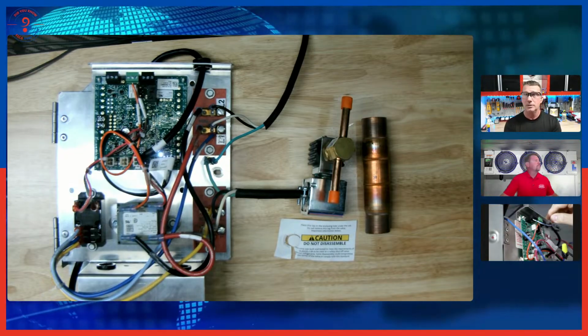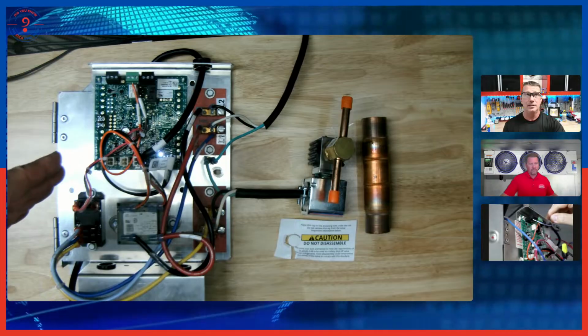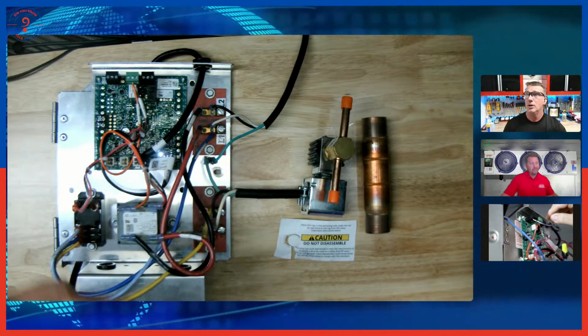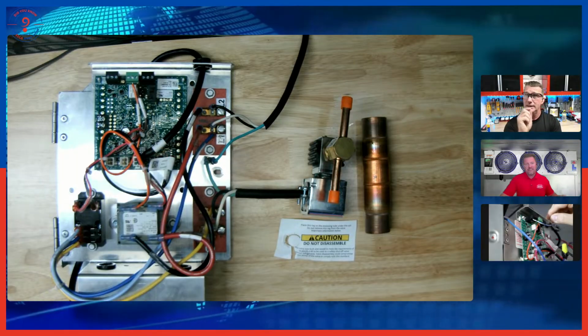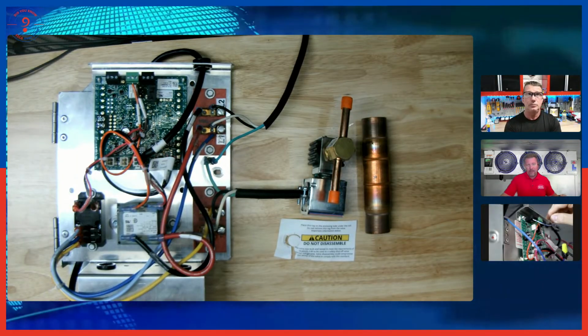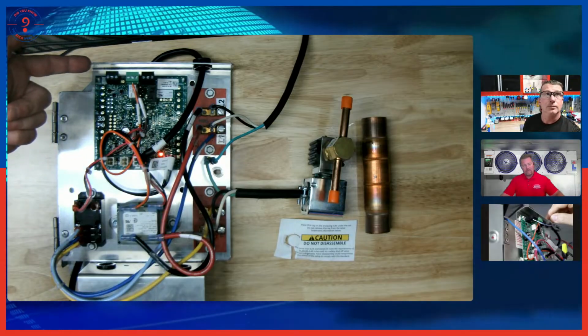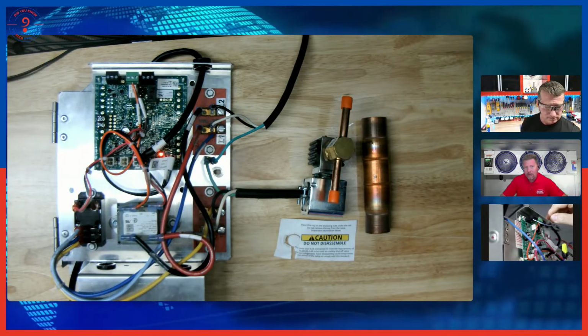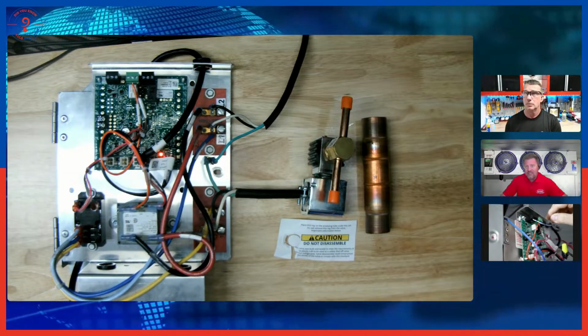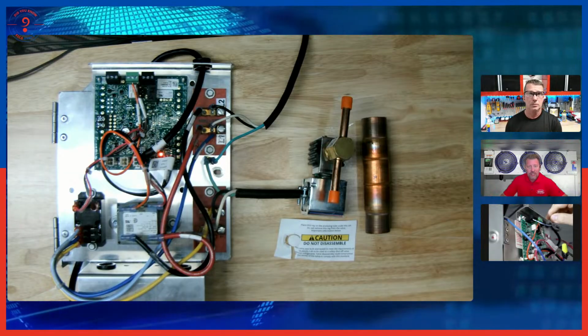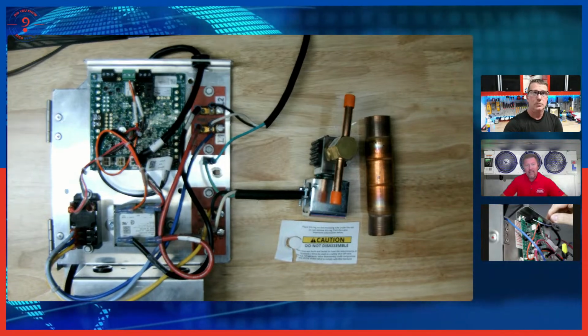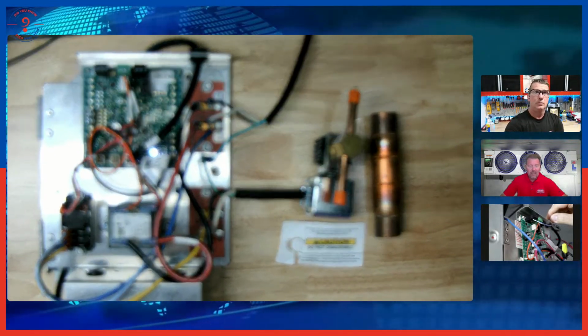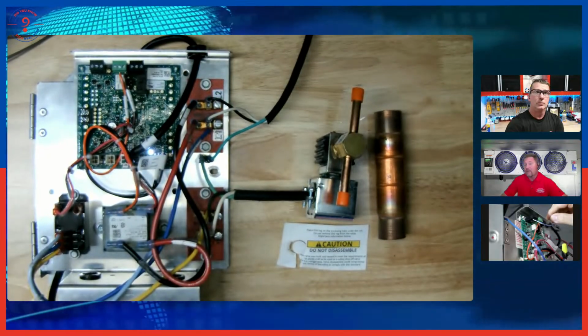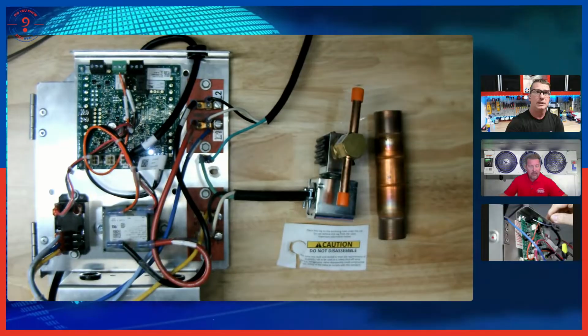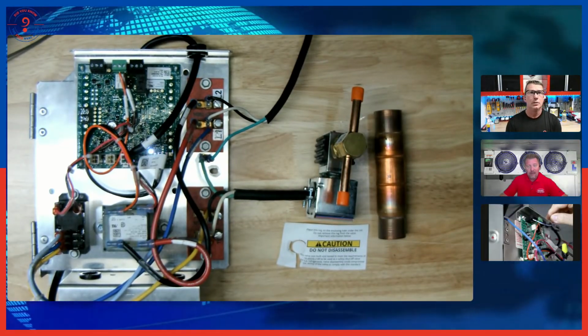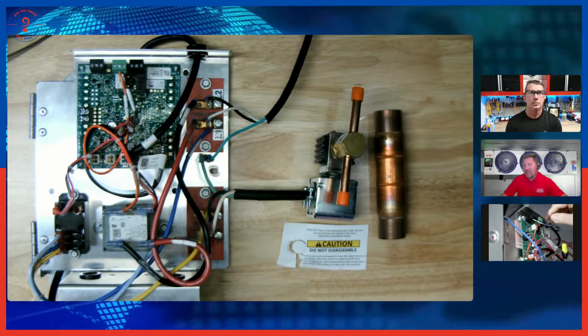So if we wanted, we could actually use auxiliary contacts to set up an alarm or notification for this. That's correct. Up there on the top, we do have those, and those are dry contacts. So they are not being powered through the control board. These would send out an external signal, basically just closing a switch, for your external alarm that would let you know, hey, there's something here that needs to be noticed. Exactly. We're not going to shut your system down yet, but there is something that needs your attention.